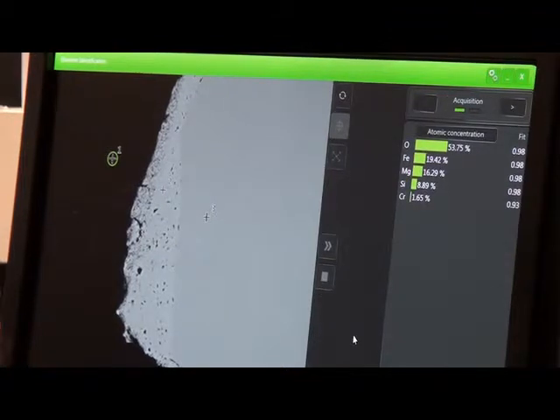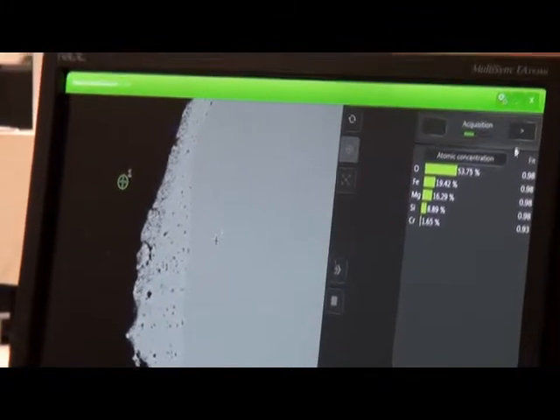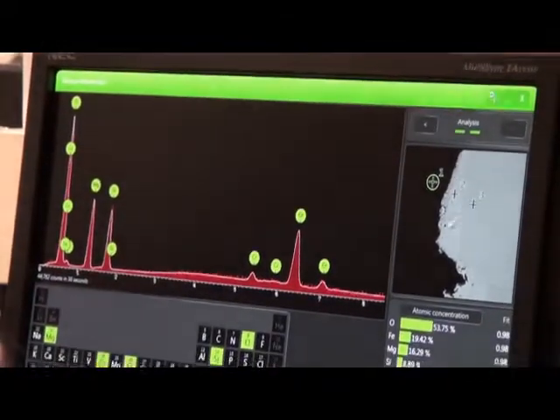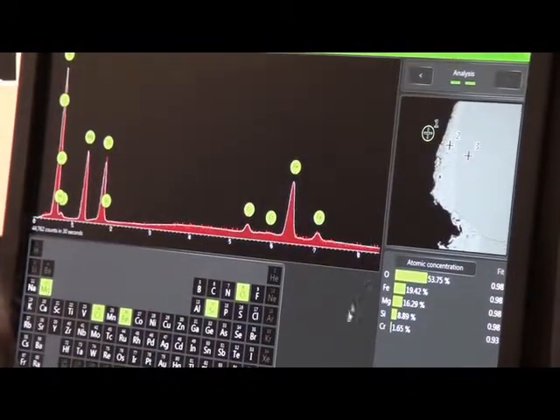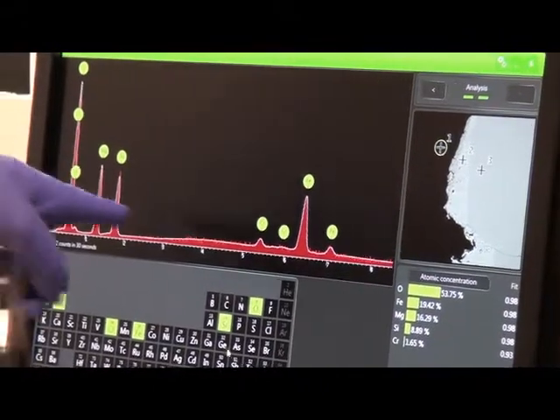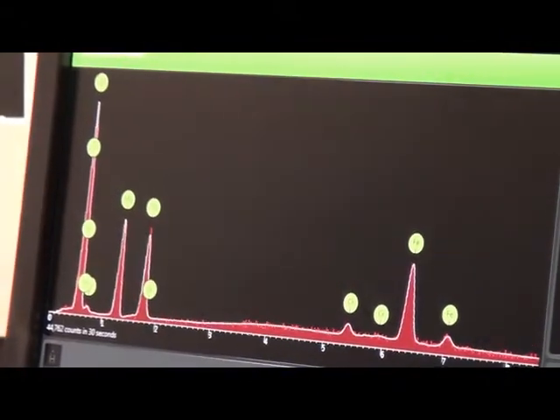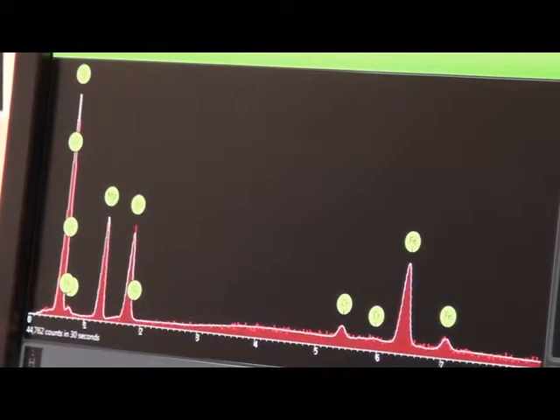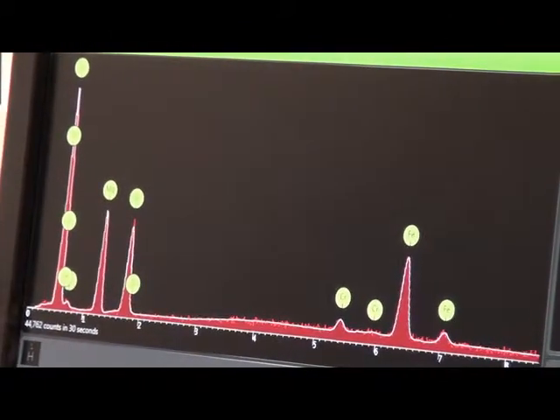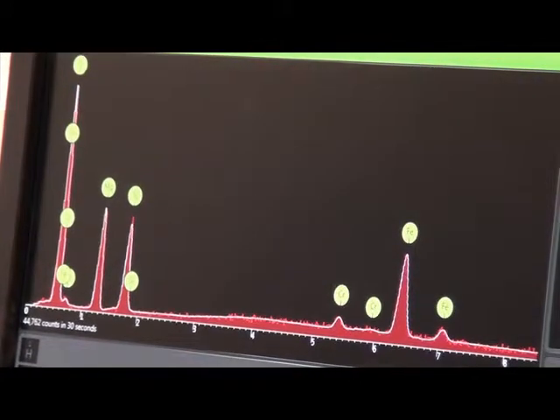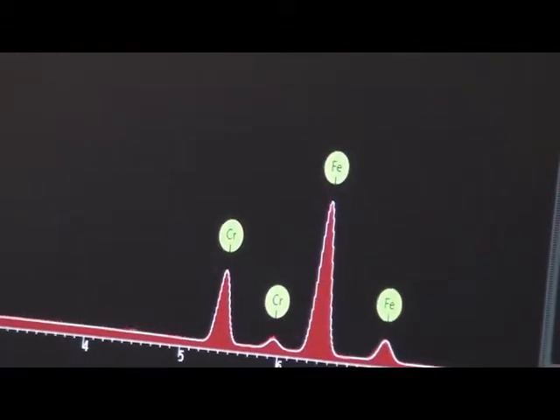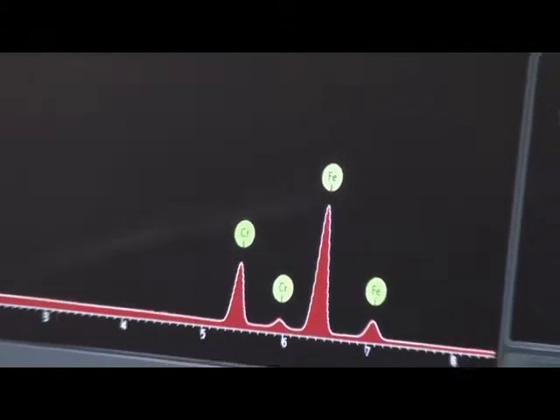One more thing I want to quickly note, if you can switch to the second screen next to acquisition, okay, this gives us a chance to actually look at the energy spectra. This is what's actually being detected in the x-ray detector. The electron beam bombards the sample and, as a happy byproduct, produces x-rays that are characteristic of the elements present. Let's choose point number three. Okay. And you can see that the computer's attempt has identified an iron phase, a chromium phase. Can I borrow the mouse for just a moment, please? Thank you.